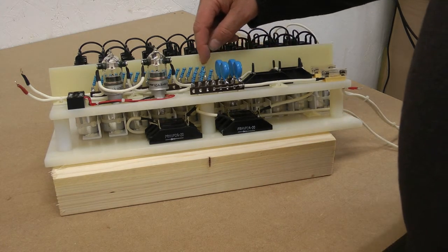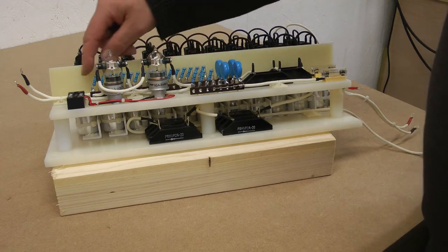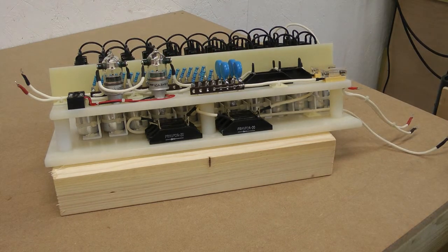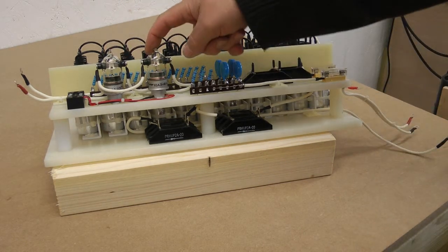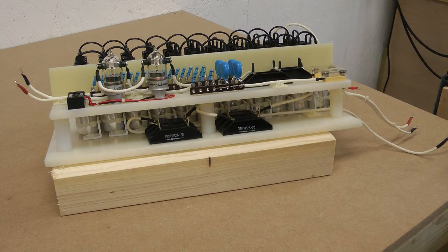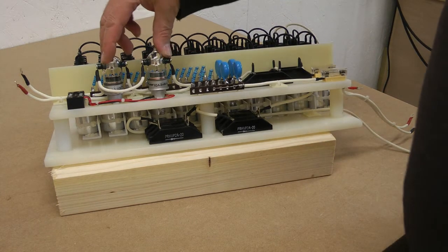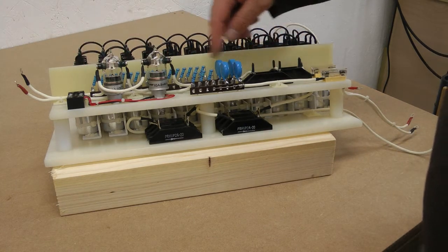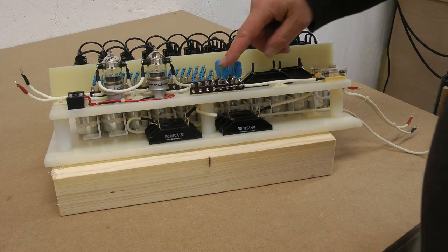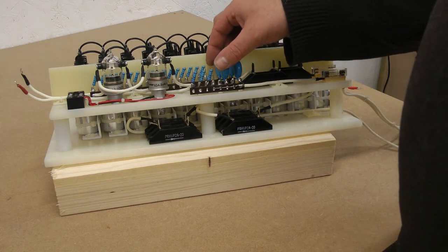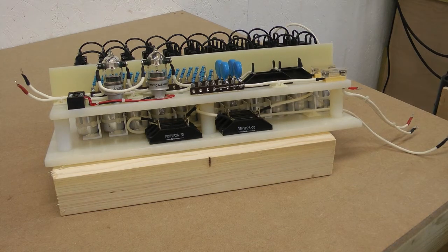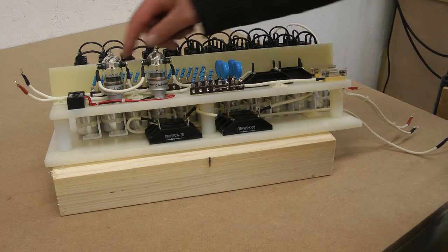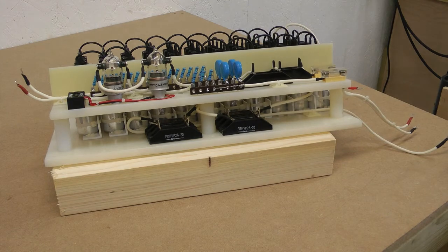That then is fed down a resistor. So ultimately we are trying to feed it down to a 1 milliamp meter, and then we have various switched high voltage feeds off of here. So to get our 5 kilovolt, 10 kilovolt and 20 kilovolt range, with both of those off, we have got 20 resistors in a loop. So it comes down through the meter, back through these. The supply is supplied here by the half wave rectifier. So that will give us 20 kilovolts going down to 1 milliamp. There's 20 1 megohm 2 watt resistors in series.